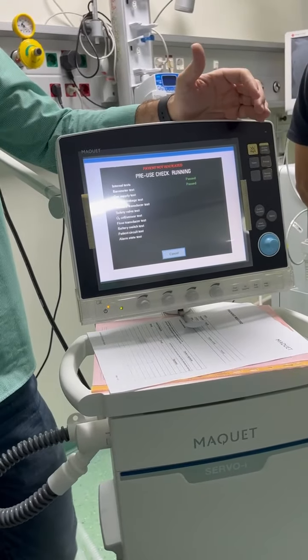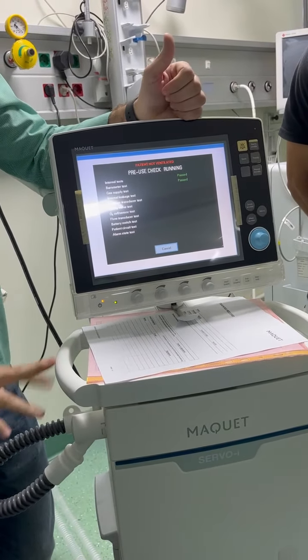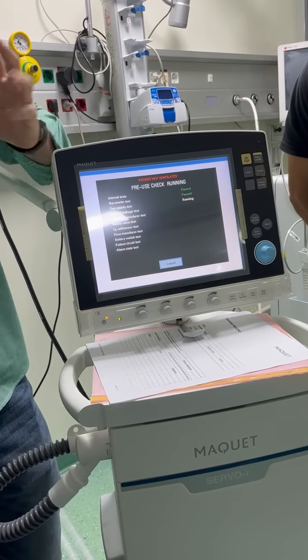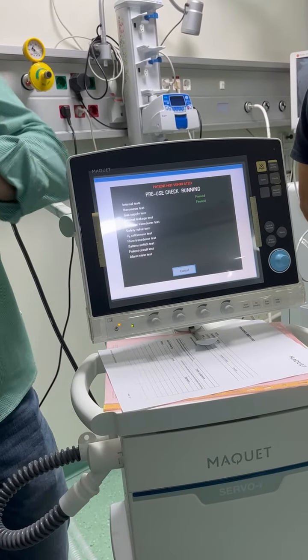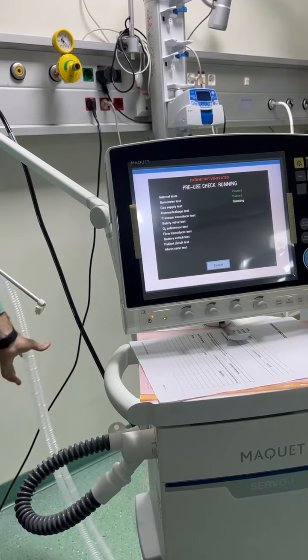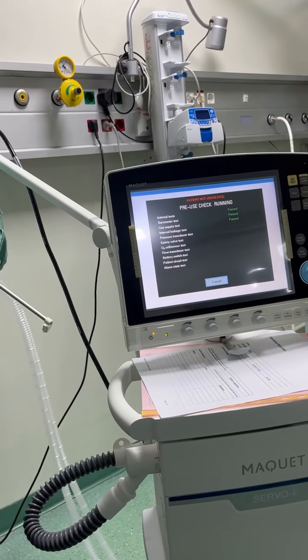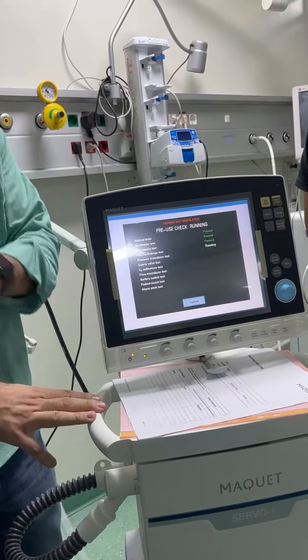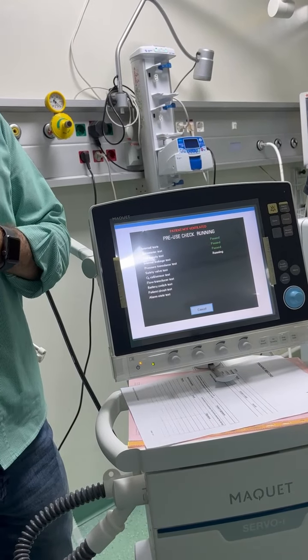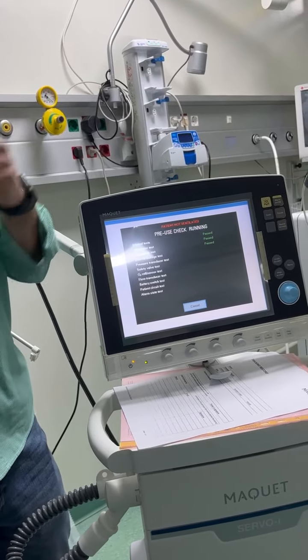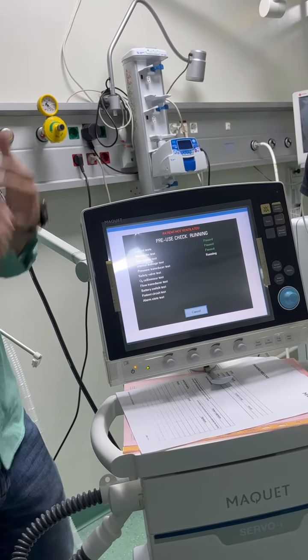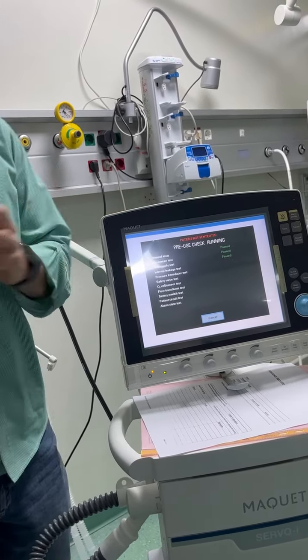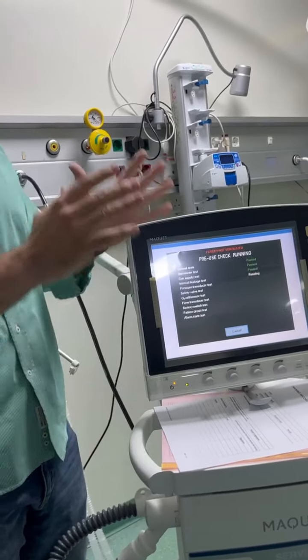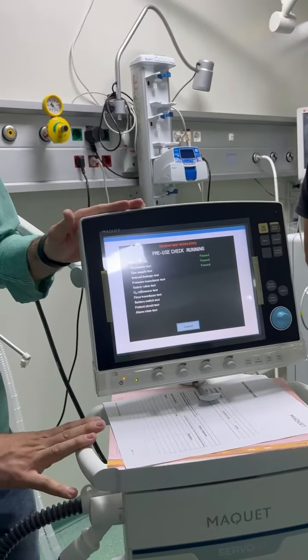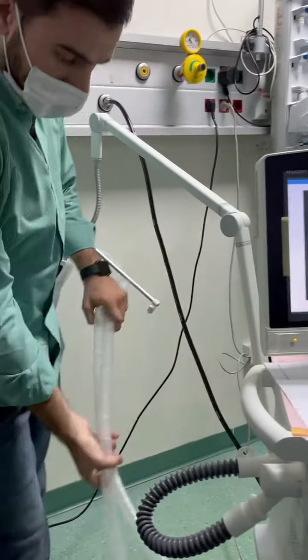On its own. Right. I have 2 or 3 conditions I need to mention. First one, the pre-use check is a must, and it has to be done with the circuit that you need to connect to the patient. For example, I cannot keep the ventilator in the stock room and tell someone I need a ventilator from the stock room, I will go there, do the pre-use check and bring it in. No. We have to bring the ventilator here to the bedside and do the pre-use check here, with the same circuit I need to connect to the patient.